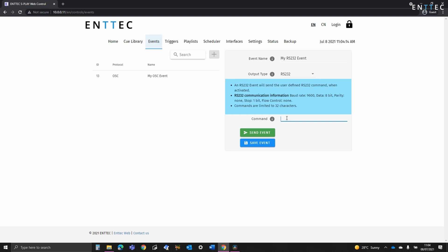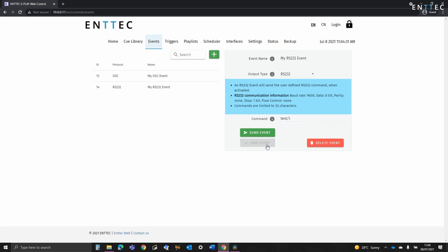So to define an RS232 event you select the RS232 event type, you give it a name and then you define the command in the box. If you want to add a line feed simply add a slash L at the end or slash R for a carriage return. Next we've got relays.